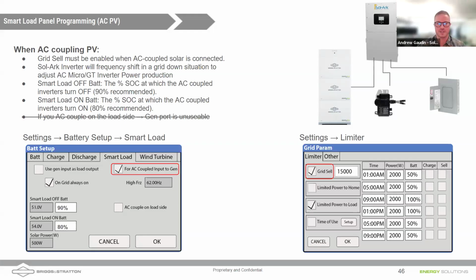I'd say that's a pretty good place to start. Once again, this can vary depending on your battery size. So if you have a larger battery, you could potentially go to 95% and 85% because you have more capacity before there may be a concern of, you know, potentially overcharging your battery. But typically I would say 90% is a safe place to set it. Yeah. And then maybe also a function of the size of the AC coupled solar array as well.